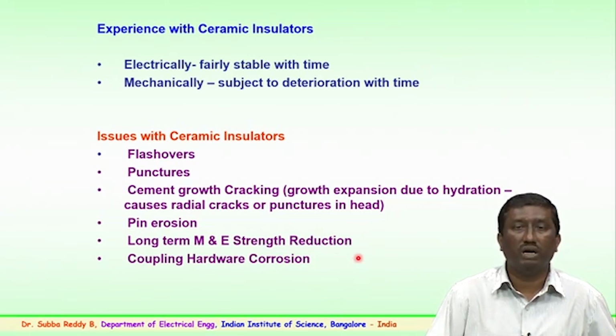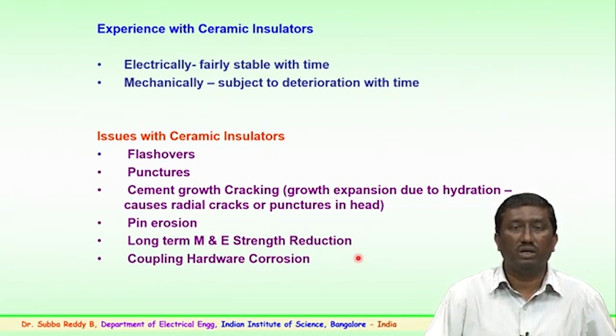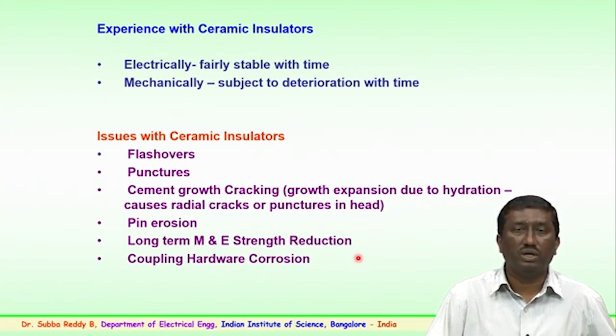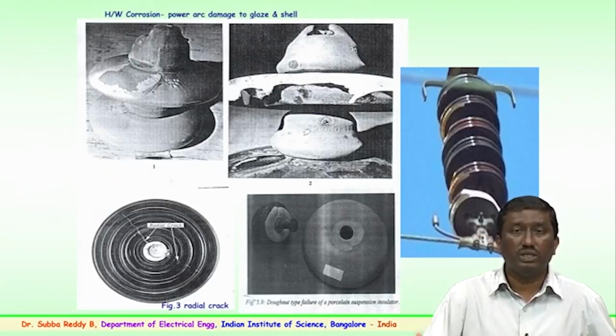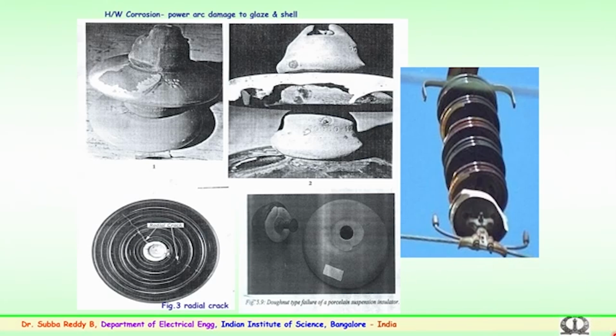And also coupling hardware corrosion. Coupling hardware is the hardware used to connect the insulator to the tower and to the conductor. We have several types of clamps and hardware, a yoke plate, corona control arms and many other items, which over a period of time, because of environmental factors, could lead to corrosion, and failure could be seen particularly with ceramic or glass insulators. So, these are some of the failures observed over a period of time in the field.